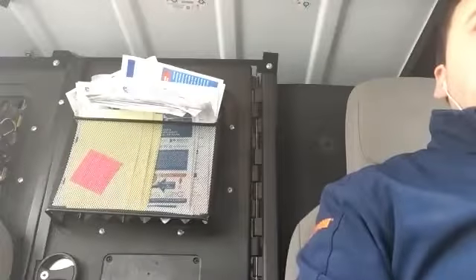Are we dropping capacity with that too? Absolutely. Okay. So if we're not running that RPM, we're only running it up to say 4,800 on medium, and we're not going up to that 6,000. Yes, we are dropping BTU capacity of that outdoor unit in the heating mode, which means our auxiliary heat's going to have to come on more. But you know, some people are okay with that. They would rather have the auxiliary heat come on a little more, pay a little more money and energy, than have that noise out at their outdoor unit.